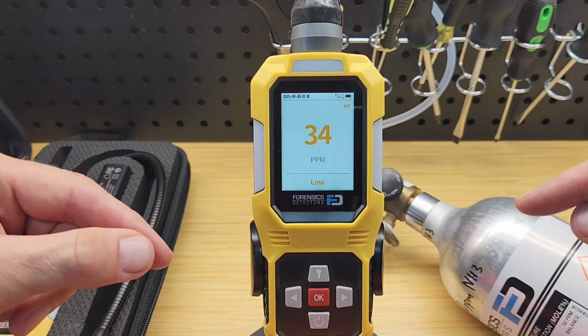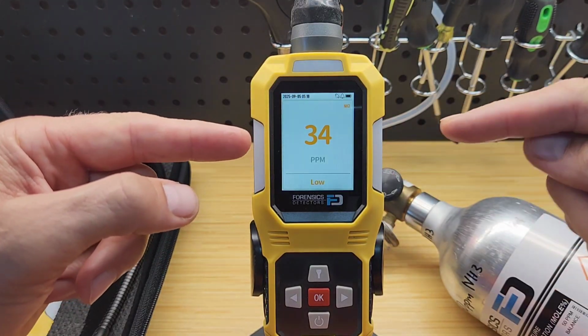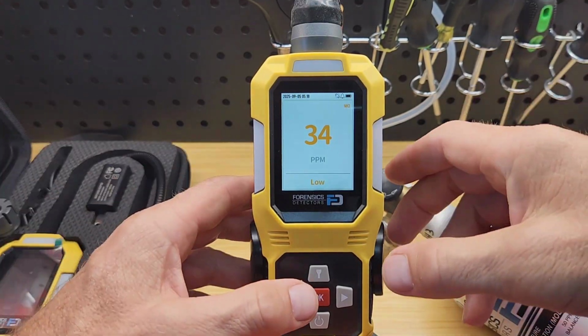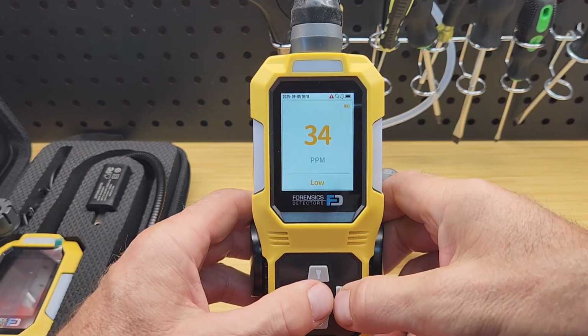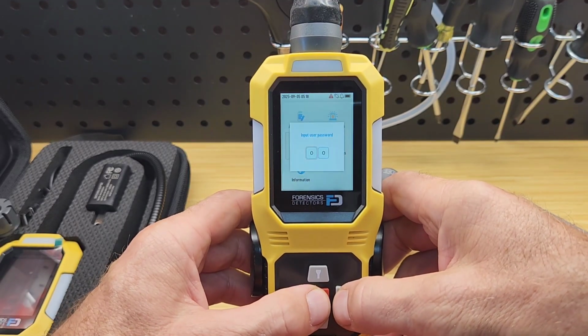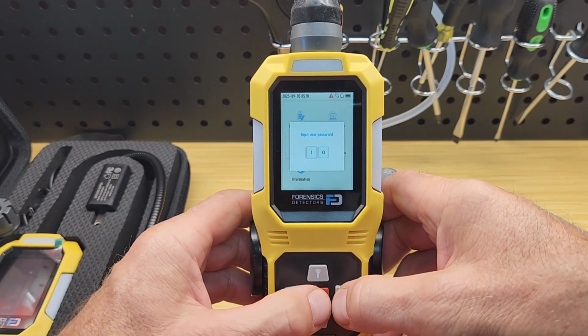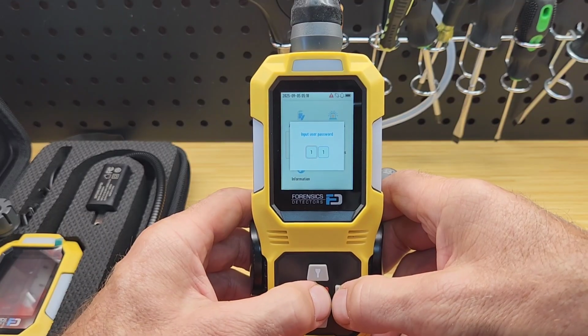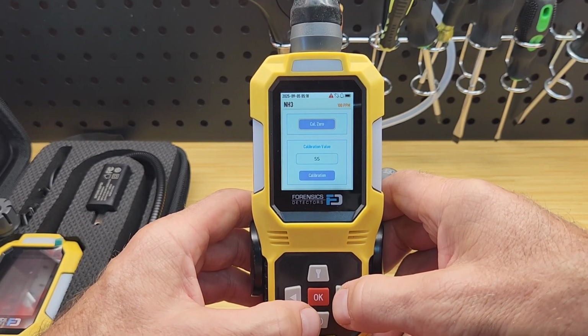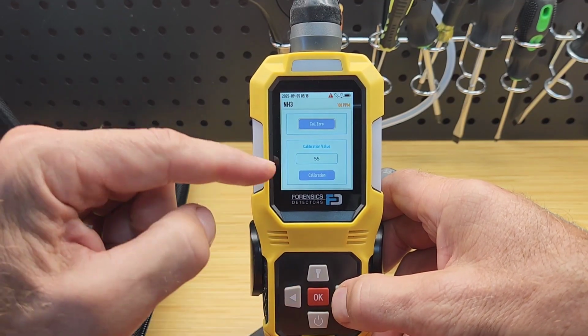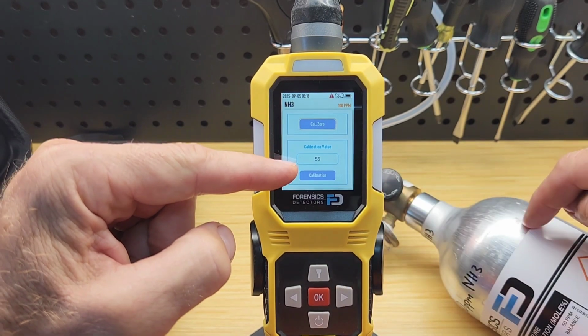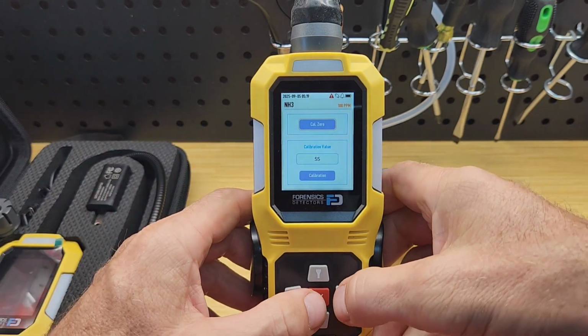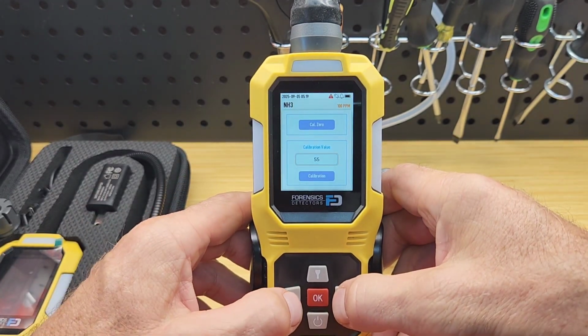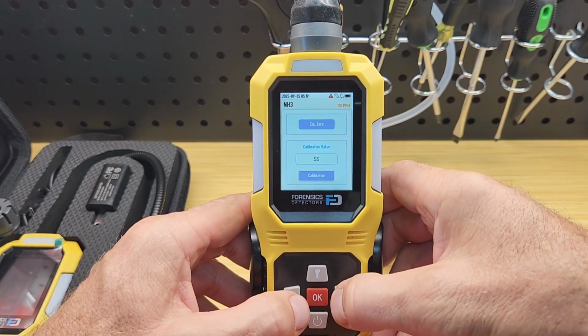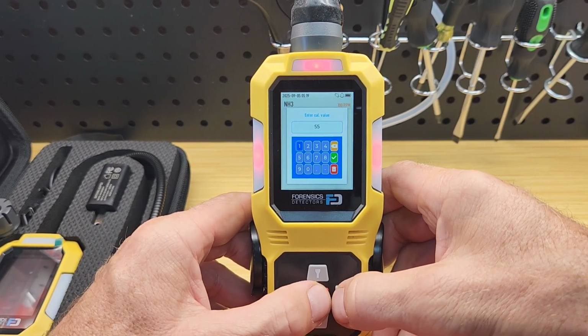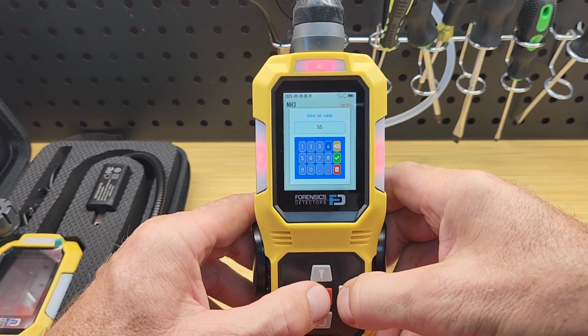We're back live. After 2 minutes, we have 34 ppm. The reference gas is 50. There is a mismatch. It needs a calibration. So let's go in the menu. Go to calibration, enter 11, and long press to get in. And then we need to go next to our calibration. We know we're bringing 50 ppm. It says 55. So we go next. We want to change that to 50.